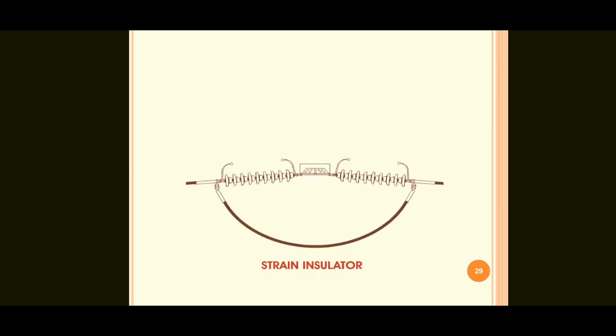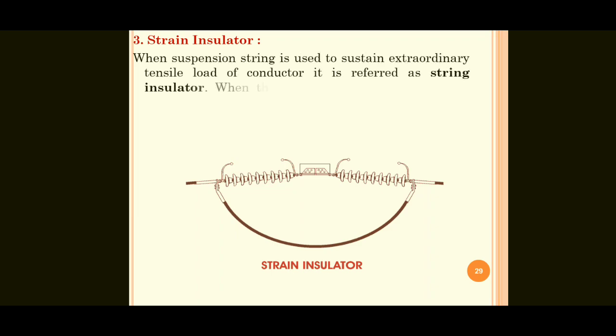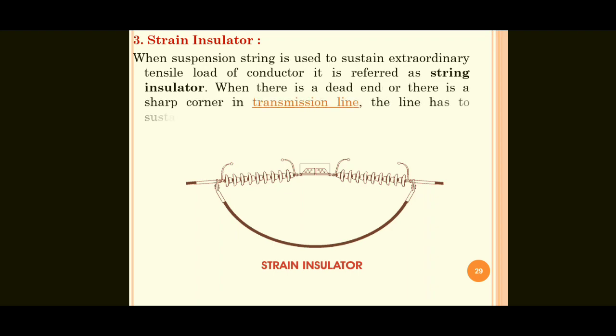So this is the main thing in suspension type insulator. Third one, strain insulator. When a suspension string is used to sustain extraordinary tensile load of the conductor, it is referred to as a strain insulator. When there is a dead end or a sharp corner in the transmission line, the line has to sustain a great tensile load of the conductor, or strain. So these are used at the dead end of the transmission line, where some tension is present at the corner. To overcome the difficulty, use strain insulators.